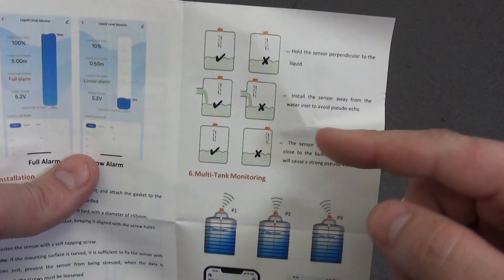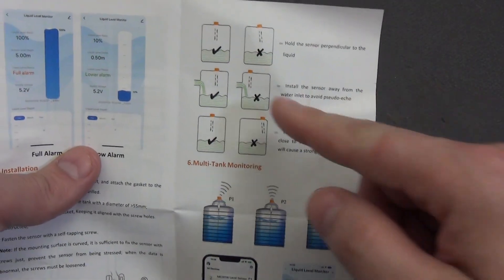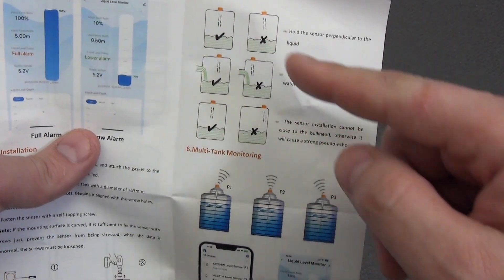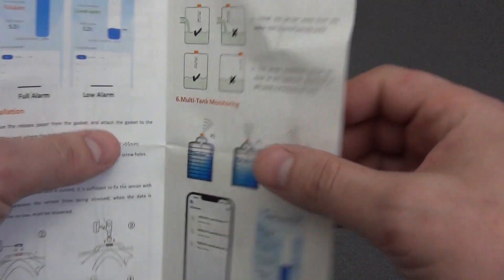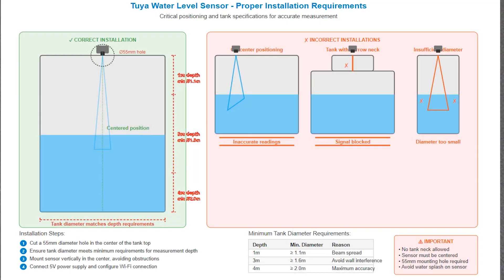In this sensor, correct installation is important. This point is in the instructions, so that the sensor is in the center of the upper part of the tank, so that when pouring water into the tank it does not block the view of the sensor. Also, the tank should not have a neck, and the minimum diameter at a depth of 4 meters should be at least 2 meters. At a depth of 3 meters, the diameter is more than 1.6 meters, and at a depth of a meter, the diameter must be more than 1.1 meter. The diameter of the hole for the sensor in the tank should be about 55 millimeters.